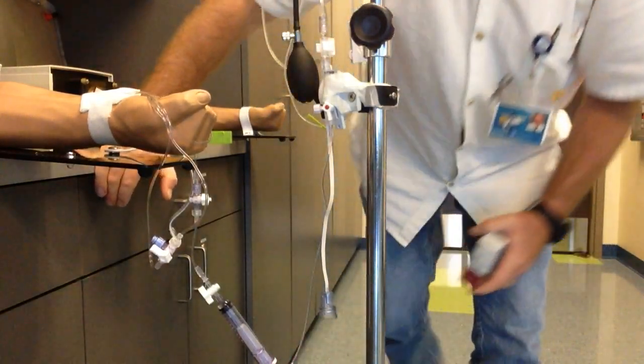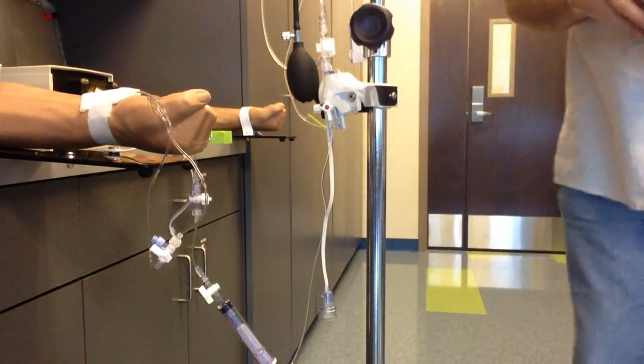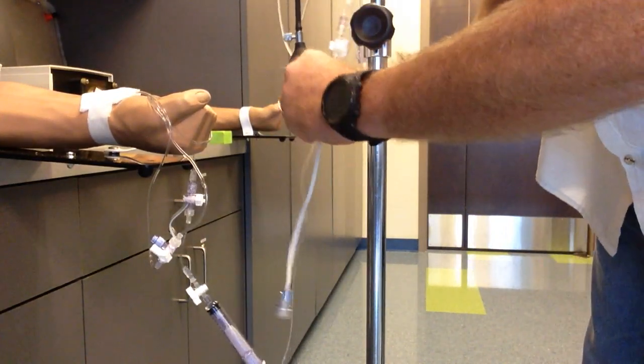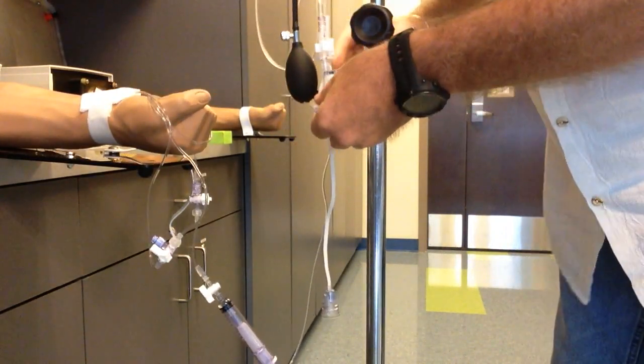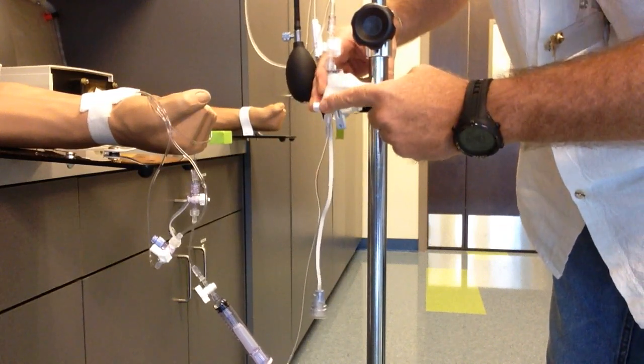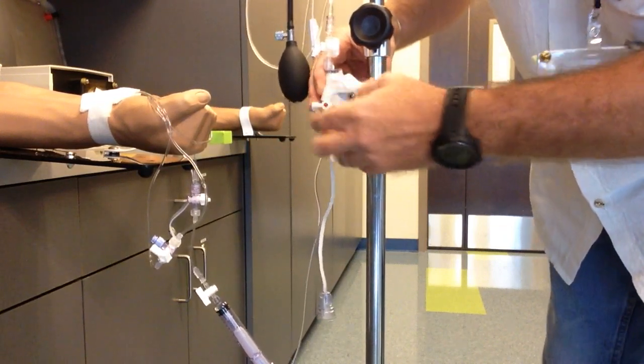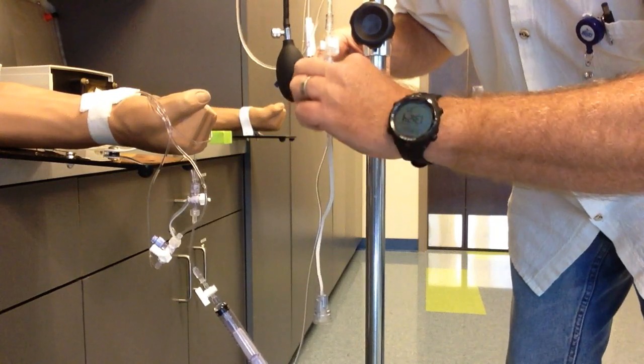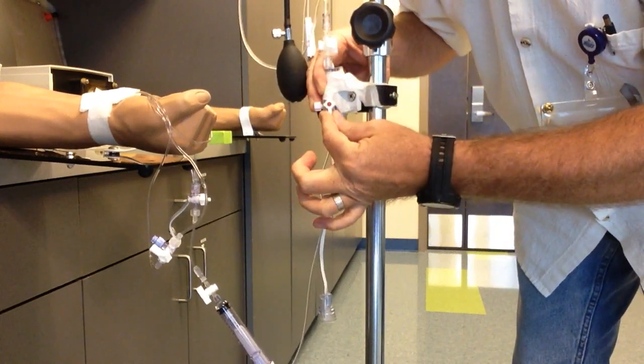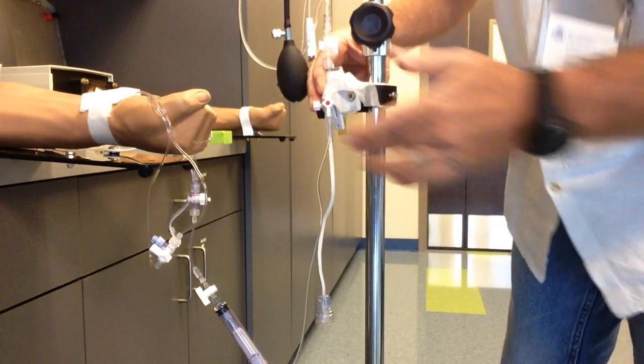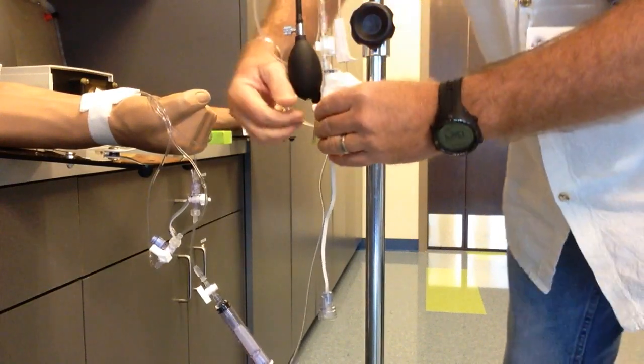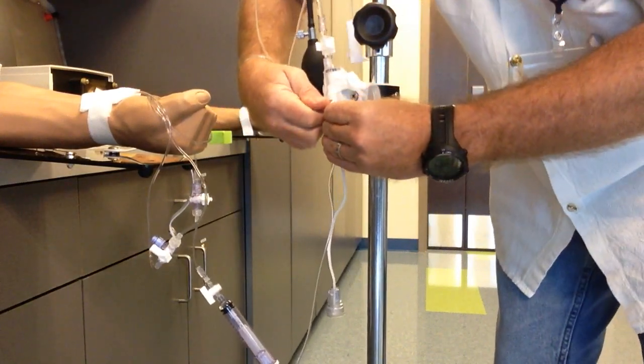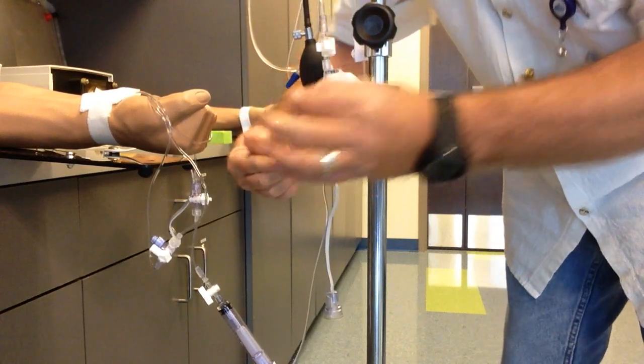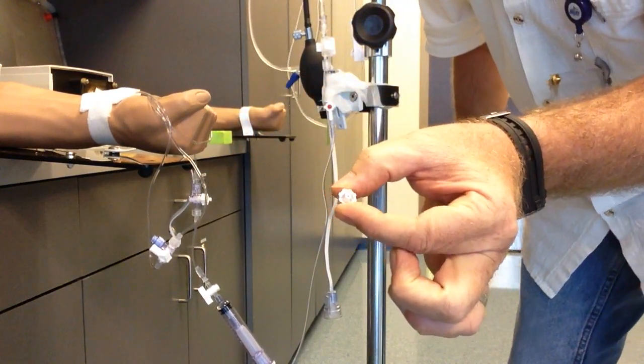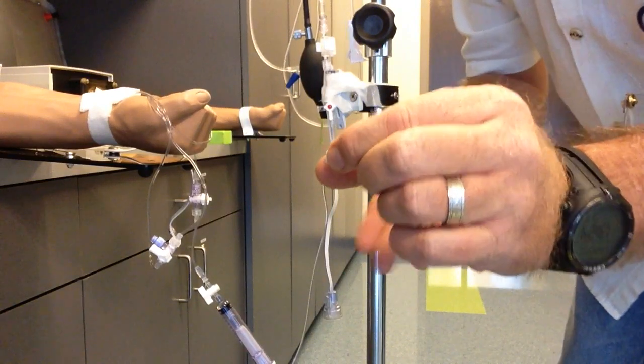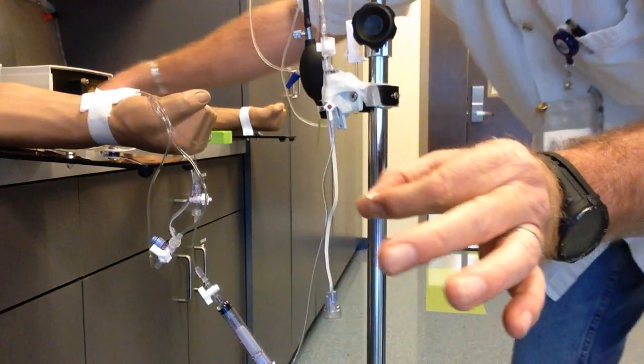So now we're going to zero. We're going to make sure that it is running correctly. So I'm going to turn here at the transducer port, I'm going to turn it off to the patient. Now there's no pressure being read. So then I will take the cap off. Some hospitals will have you change the cap every time it comes off. Wherever you are, whatever the policy, don't be touching that.